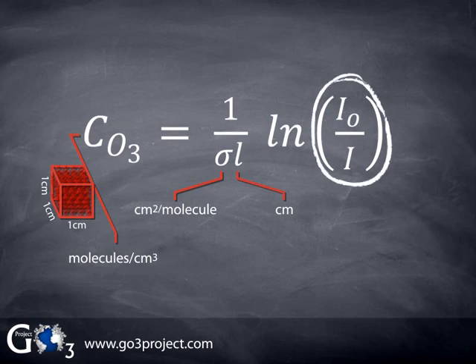Notice that the measurement is based on a light intensity ratio. Thus, we can express light intensity in any units. We could use absolute units for light intensity such as lumens, but since the units cancel, we can simply use the electrical measurements of the current produced at the photodiode in amperes, or we can measure the voltage resulting from that current passing through a resistor. In all cases, the units cancel. All that matters is that the light detector, in this case a photodiode, output a signal that is linearly proportional to light intensity.